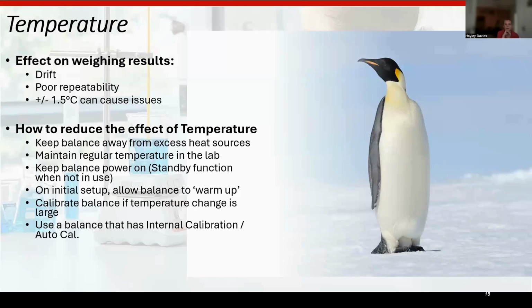Temperature can also affect weighing results, causing drift, unstable readings, and poor repeatability. It only takes a change of plus or minus 1.5 degrees in the weighing environment to cause an issue with repeatability and drift, so we need to keep the balance away from excess heat sources.